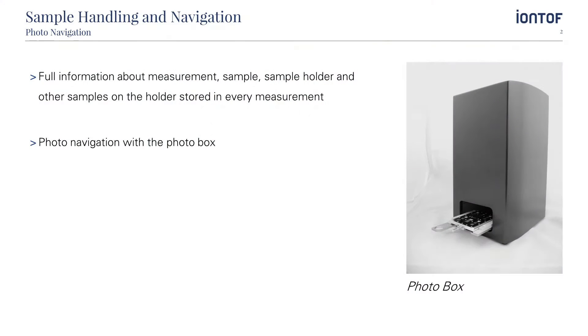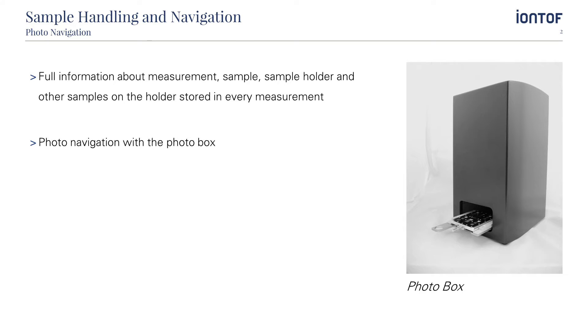In SurfaceLab, full information about the measurement parameters, the sample, the sample holder and other samples which have been on the holder at the same time are stored in every measurement. Furthermore, with the IONTOF photo box a high resolution photo of the sample holder is taken and ensures precise photo navigation in the instrument.